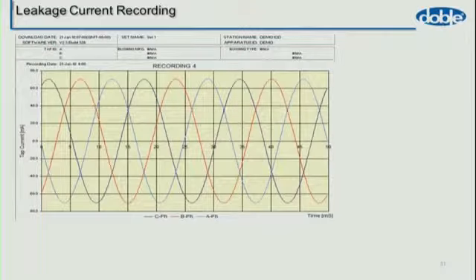How would condition monitoring help with those things? You can measure the leakage current through the bushings, relatively easy to do. You'd expect the leakage current through the bushing to be the same on all three phases and to be about the same size.